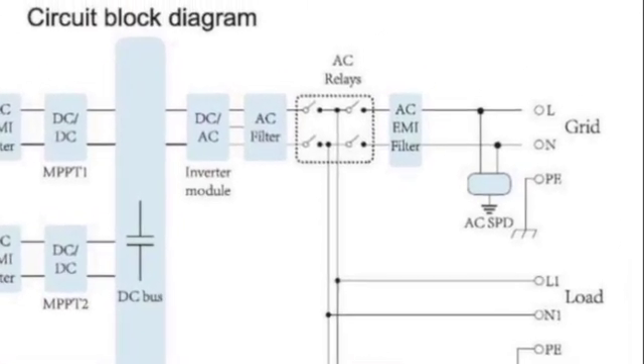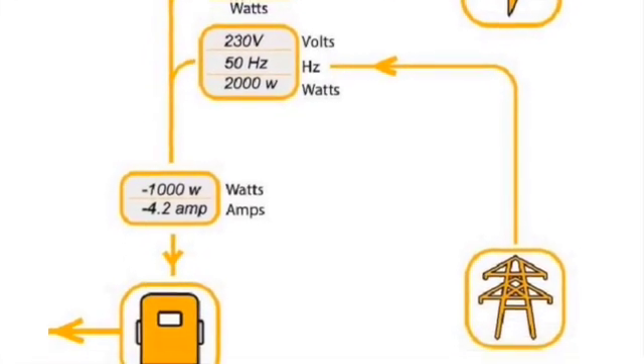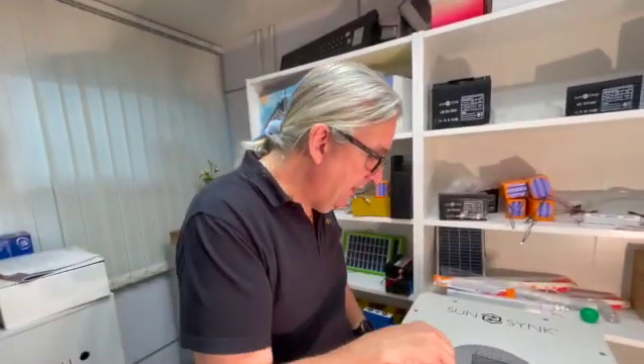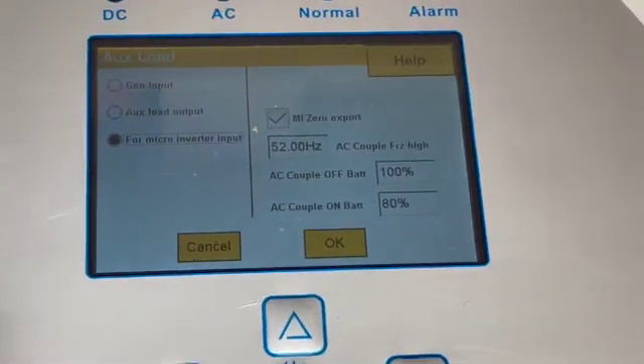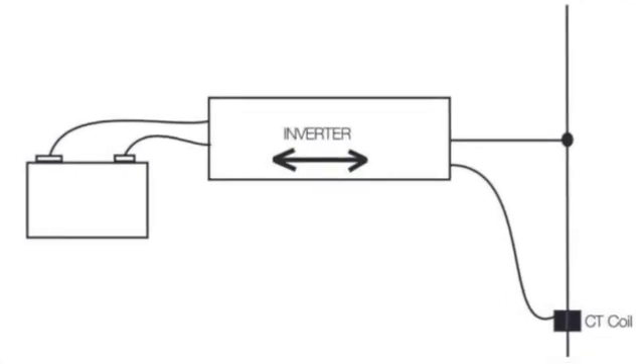The auxiliary connection and the load are essentially all on a common bus bar controlled by a relay. In this micro inverter function, the micro inverter will supply the load directly. The main inverter can only do one thing at a time — either charge the battery or discharge it. You can't have the micro inverter simultaneously charging the battery and supplying the load while the inverter is also supplying the load, because the inverter would have to reverse. That's a very important point to remember.